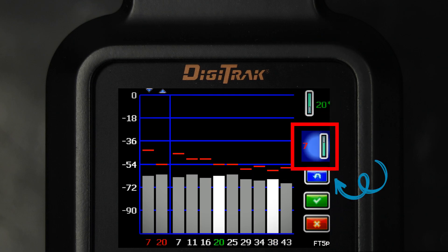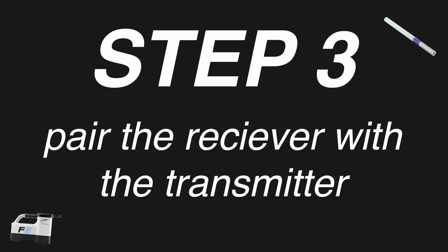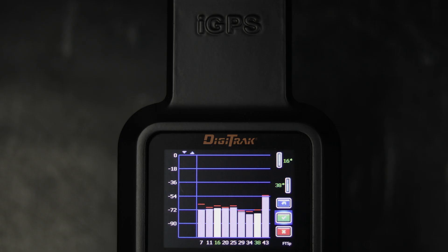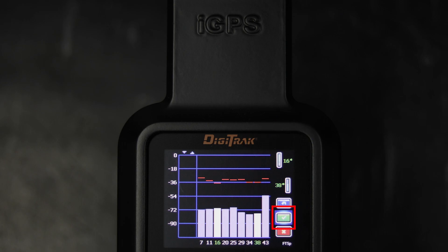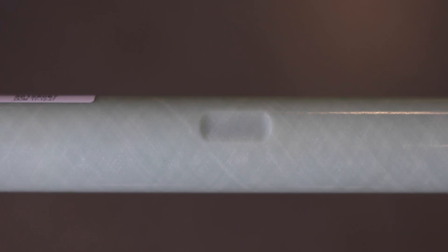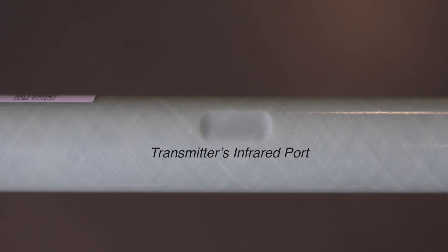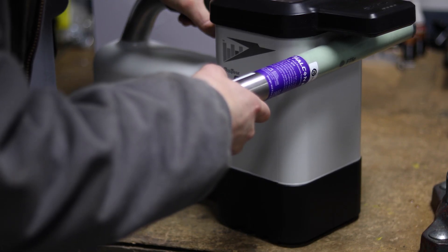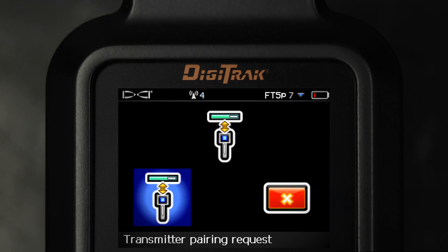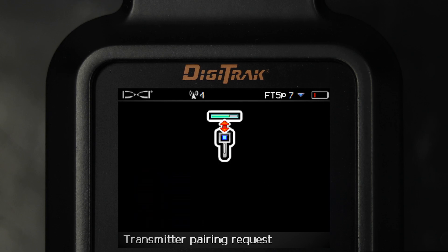Optionally, set the second band as the opposite. Step 3: Pair the receiver with the transmitter. Install the transmitter batteries and the end cap. The increase in frequency optimization noise readings shows that the transmitter is on. Select the checkmark to pair. Position the transmitter's infrared port within two inches of the receiver's infrared port. Select Pair to open the infrared pairing menu, then again to pair the receiver frequency band to the transmitter.